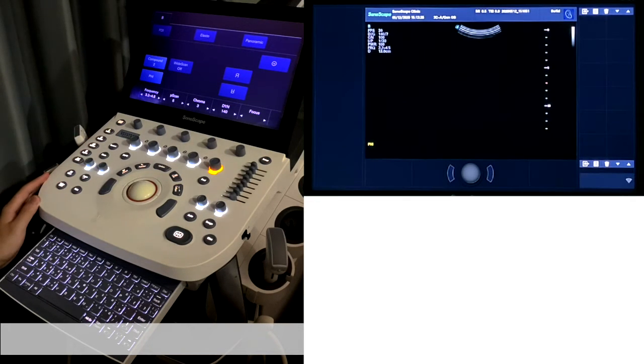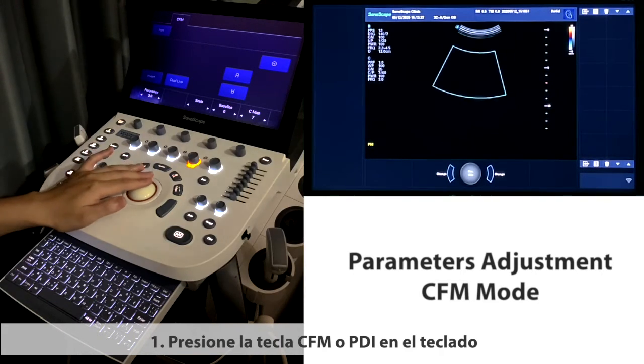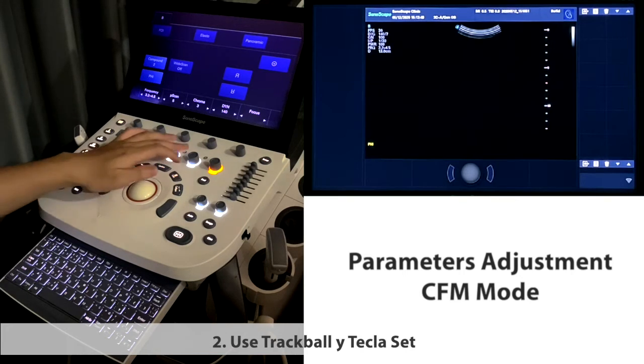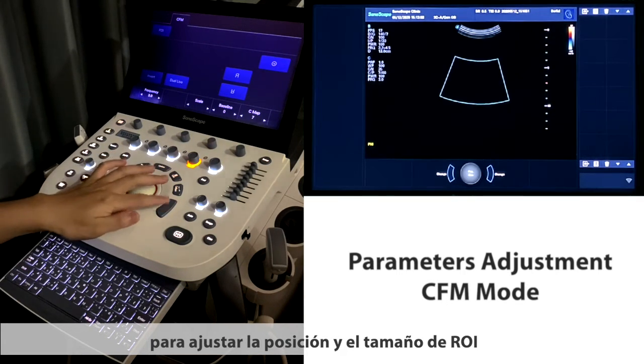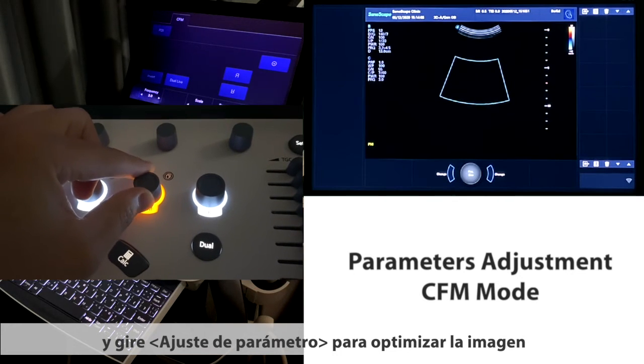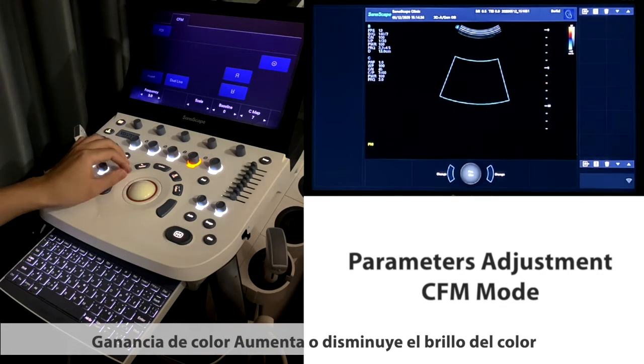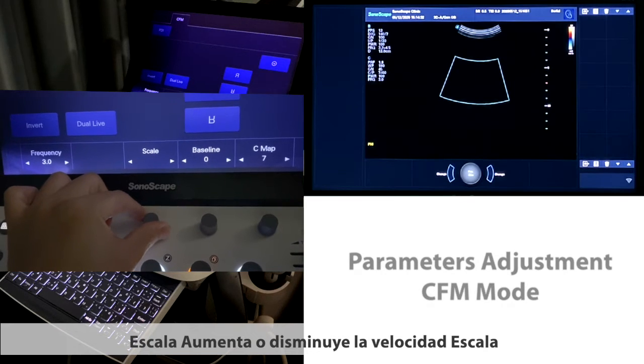For CFM mode parameter adjustment: press the CFM or PDI key on the keyboard to enter CFM or PDI mode. Use the trackball and set key to adjust the position and size of the region of interest box. Rotate the CFM button to adjust the gain and rotate the parameter adjustment knob to optimize the image, including increasing or decreasing display gain and adjusting the velocity scale.